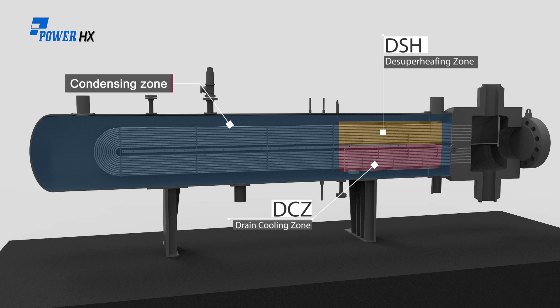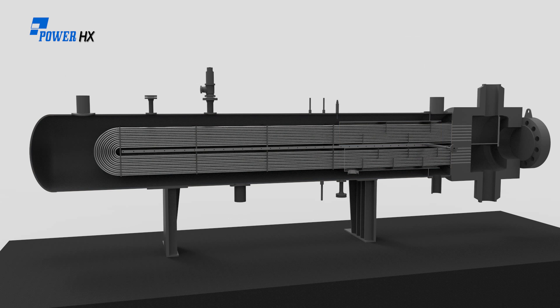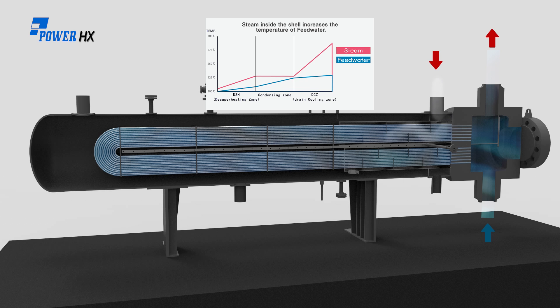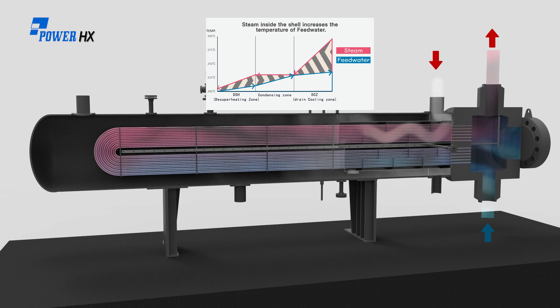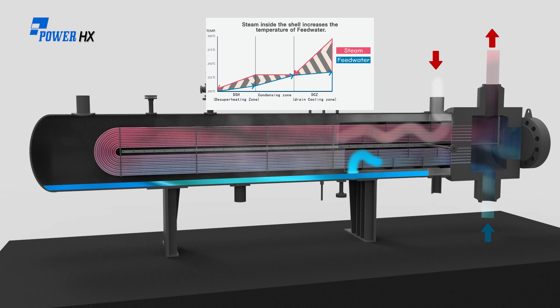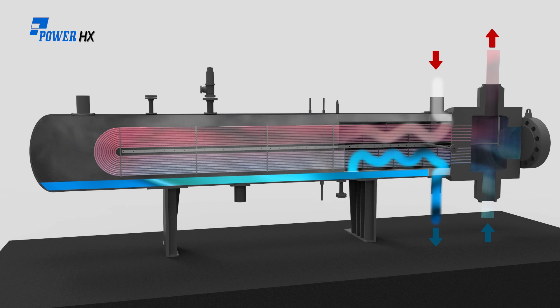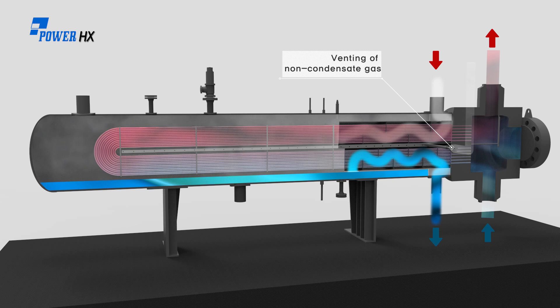For a three-zone feedwater heater: feedwater flows into the tubes through the feedwater inlet nozzle. As steam flows in through the steam inlet nozzle, the steam inside the shell exchanges heat with the feedwater, causing its temperature to continually increase. Non-condensate gases, which decrease the performance of the feedwater heater, are released. Keep the vent nozzle open while operating the feedwater heater.